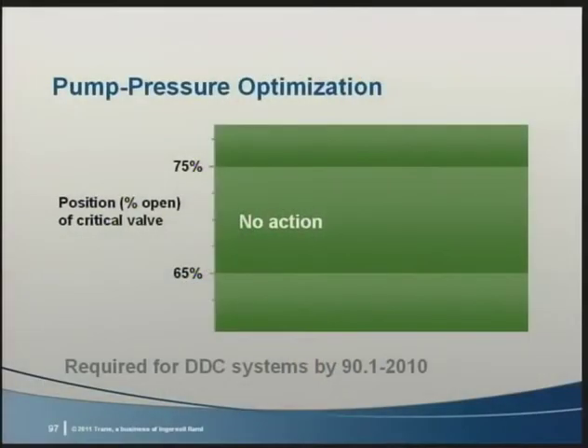The DDC controllers indicate the position of their individual control valves. The building automation system continually polls the DDC valves at the coils, looking for the most open valve. It then resets the pump static pressure set point so that at least one valve is nearly wide open. As a result, the pump generates only enough pressure to obtain the required flow through the critical terminal unit. This graphic shows the simple control logic.